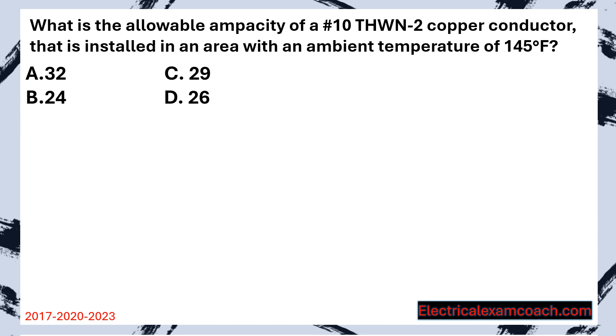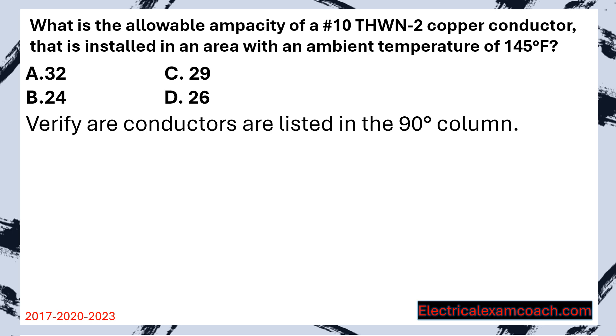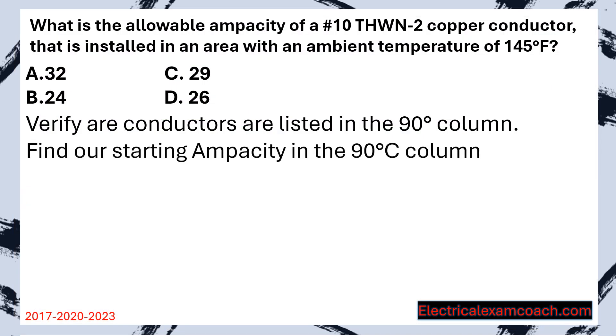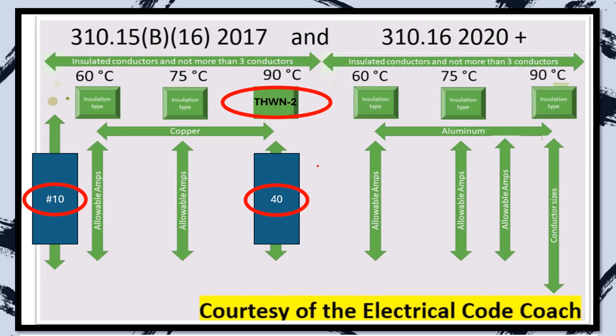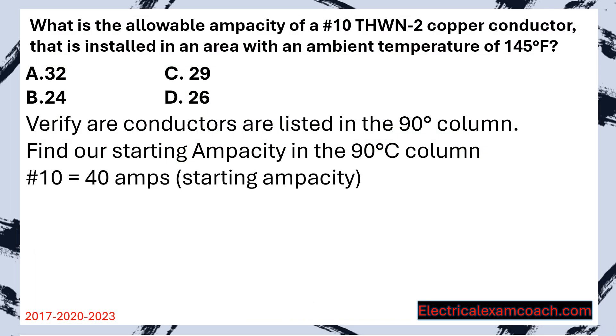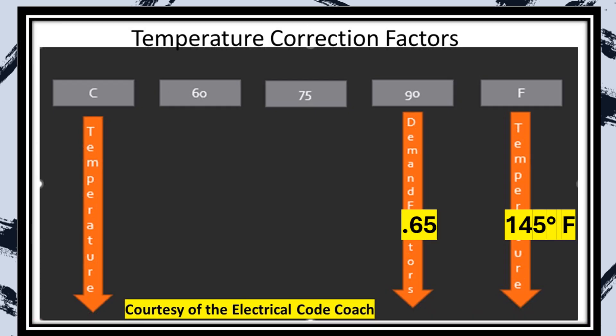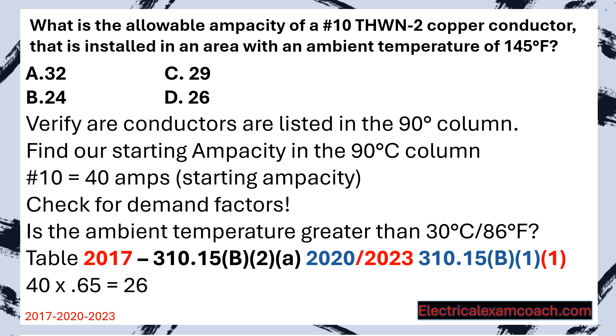Next problem: What is the allowable ampacity of a No. 10 THWN-2 copper conductor installed in an area with an ambient temperature of 145 degrees Fahrenheit? Step 1, verify THWN-2 is in the 90 degrees C column — it's there. Find the starting ampacity: No. 10 crosses over to 40 amps. Check for demand factors — ambient temperature is greater than 86°F, so there is one. Go to the corrections table, start on the right-hand side, find 145 degrees, slide over to get a correction factor of 0.65. Multiply 40 by 0.65 for a new allowable ampacity of 26 amps. Select D.